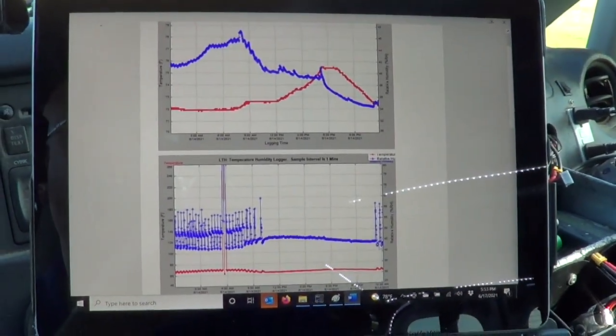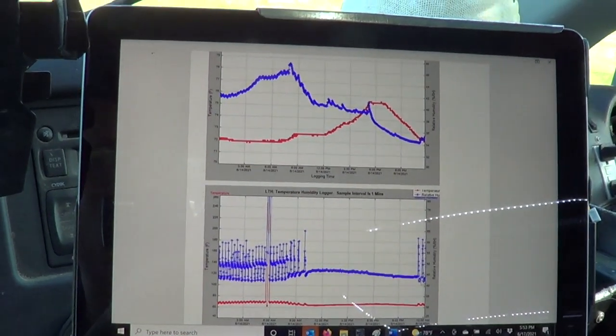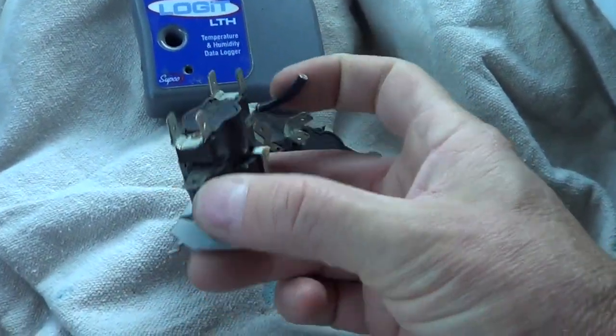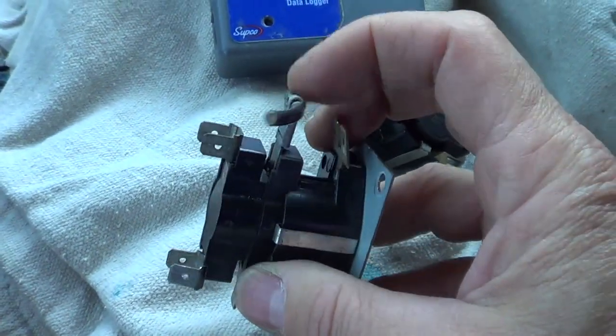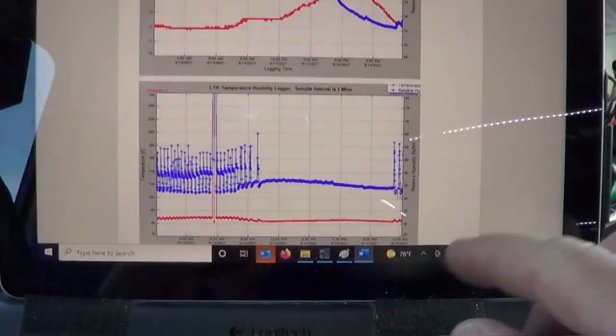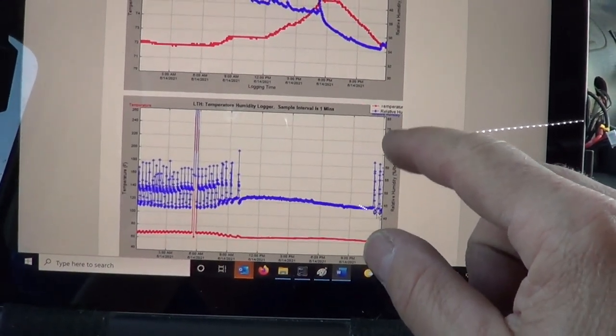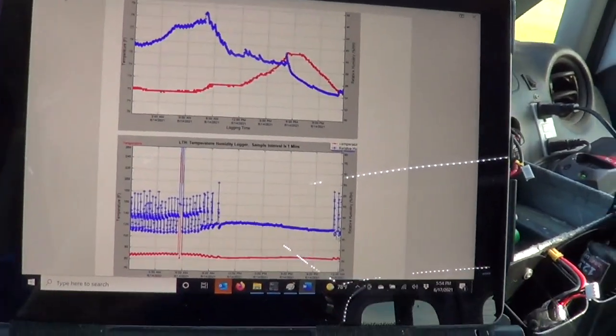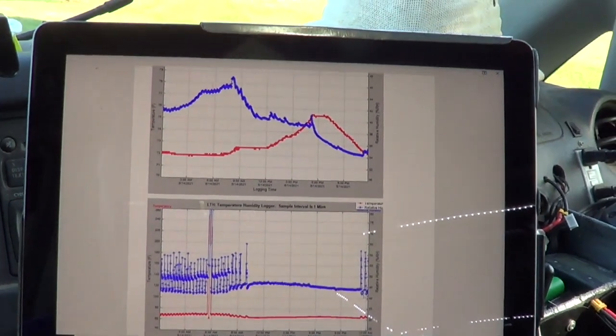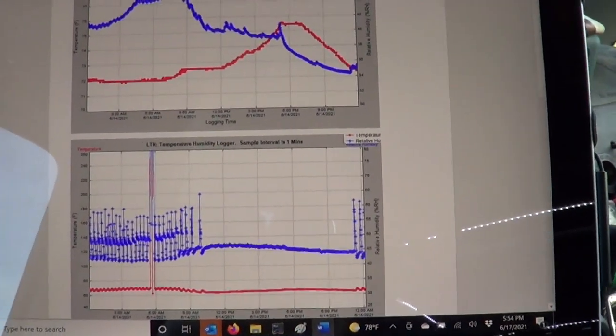Then as the weather peaks and cools down, it doesn't start cycling again until night. So this is a capacity issue — something killing the capacity. When I looked closer, I found that 5 kilowatts of heat was staying on because of the sequencer having a short — the terminal shorted. A clue is how low the humidities are: supply temperature is in the 50% humidity range, and normally supplies are going to be 80 to 100. Technically supply air is usually always 100% humidity — it's called saturated air. I put the data logger on, came back, and it was fairly obvious. The unit was staying on; we just had a capacity issue. It took me 10 minutes to figure that out with the data logger.